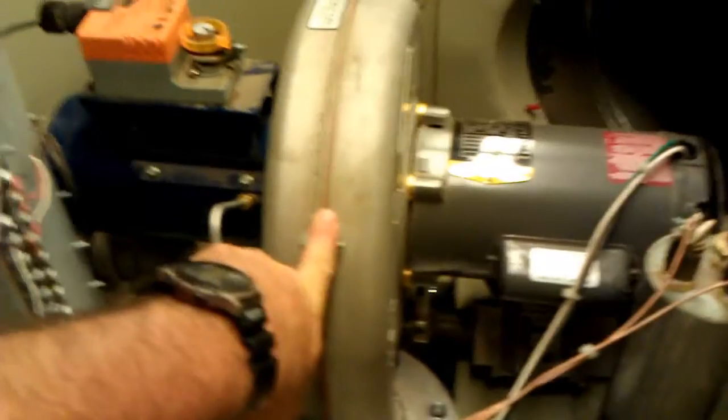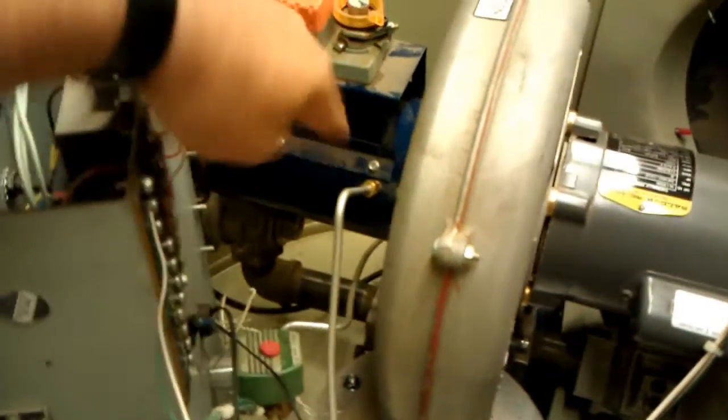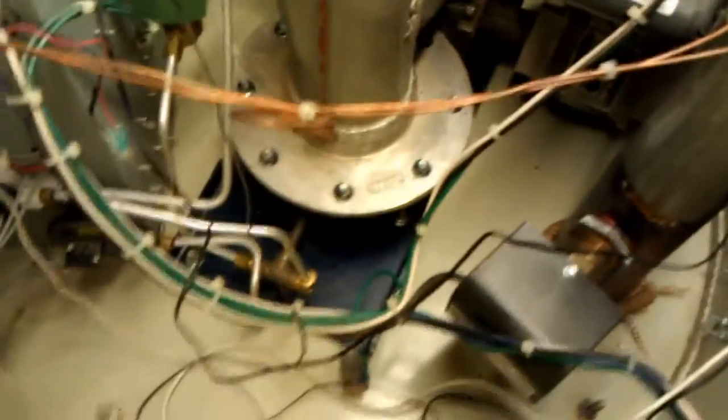Took apart the inducer blower section. This one has a modulating air baffle for the variable air flow, variable capacity, which uses pressure over here to a regulator, gives reference pressure over here to this regulator, which then maintains the correct fuel to air mixture. These are pretty interesting.